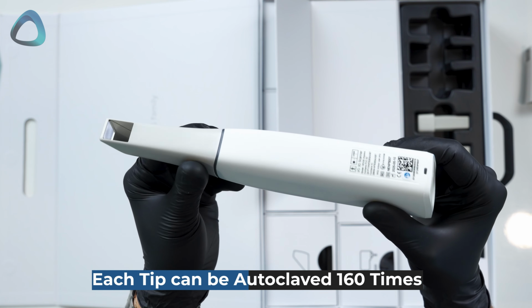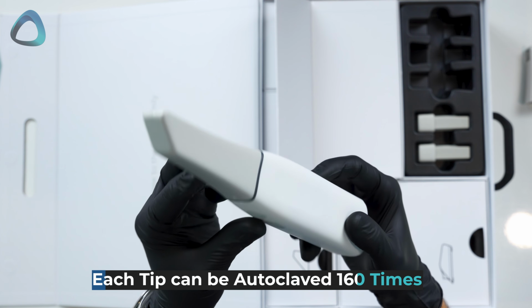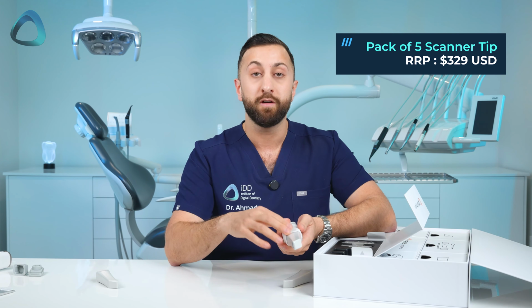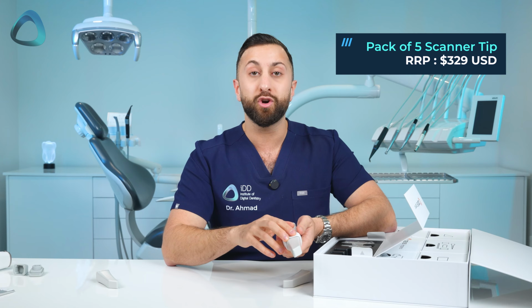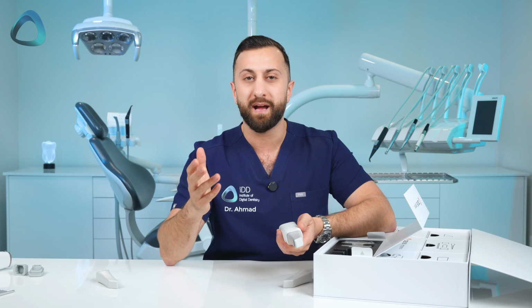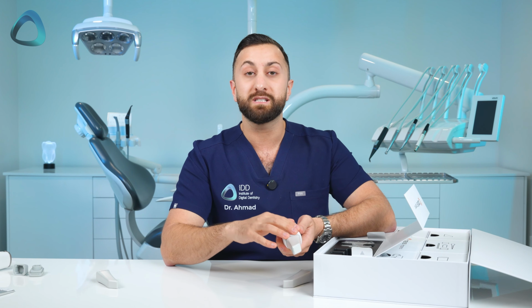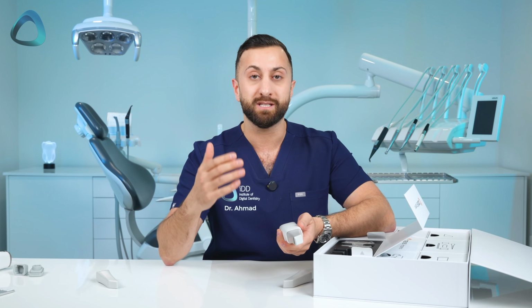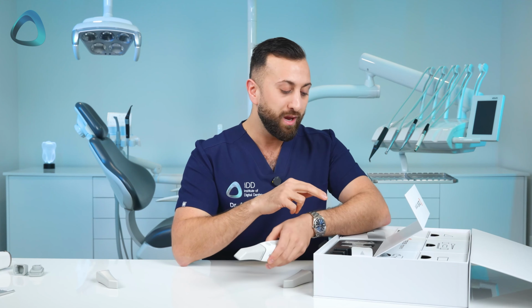Now, a couple of things about these scanner tips. The company says they can withstand up to 160 autoclave cycles, and they cost approximately 329 USD for a pack of 5. In other words, 66 USD or thereabouts per tip, and that means 40 cents per patient based on the autoclave cycles.